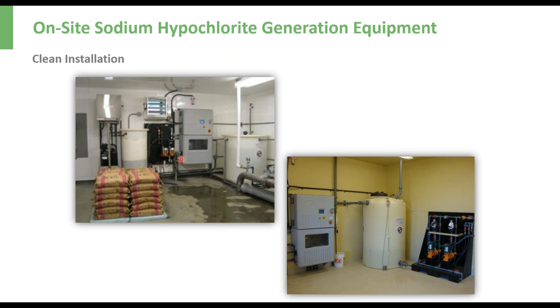If you can see on this particular installation right here, what's cool about on-site generation is that most states have a 30-day chemical storage requirement. Well, this client up here in the upper left-hand corner had that requirement, but we maintained that with a pallet of salt in the generating room, and did not mandate that the brine tank right here have to hold the 30 days of salt, as long as the 30 days was within the generating room. So that just makes life easier and helps reduce the overall capital cost of it.